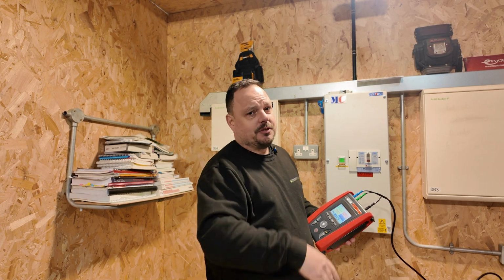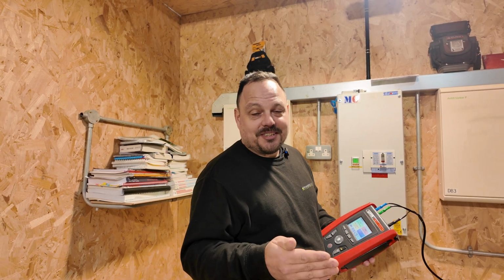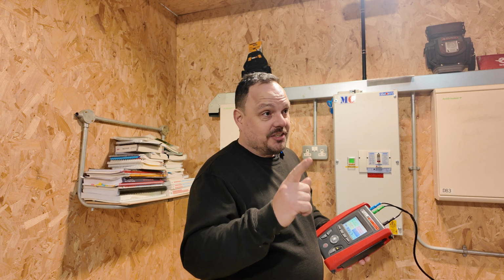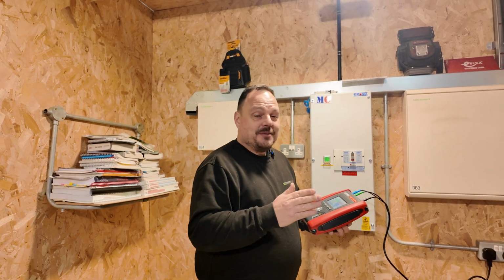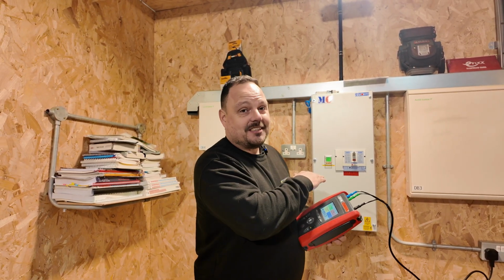Now I have to say here we do have lots of stage RCDs because I was super paranoid about trainees coming in here, and if we had any kind of fault happening, even down here at the bays, I'd like the power switching off as far back as possible to alert people to that issue. So that's the way I've set it up. The logic to that 2 years in maybe wasn't as needed as I thought it was at the time, but we're here now. I can't change that. So it's what it is. So when we do this test, we may operate this in its own right.